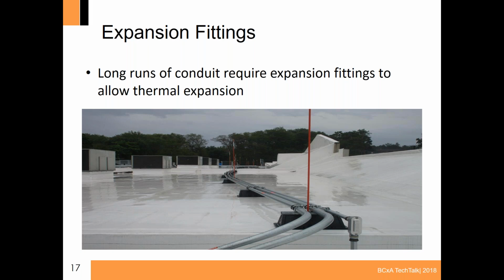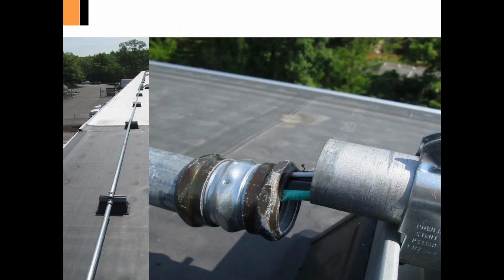So what we're looking at here is an extreme example, but this conduit had actually shifted over to the left approximately 10 feet due to the thermal expansion and contraction that had gone on. That's why, again, doing a little bit of math, looking at the electrical code, and understanding if we do need the proper fittings to account for that is important.